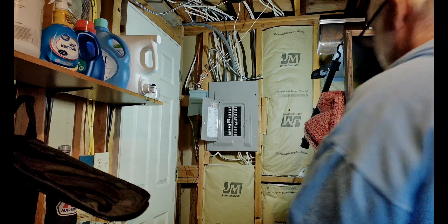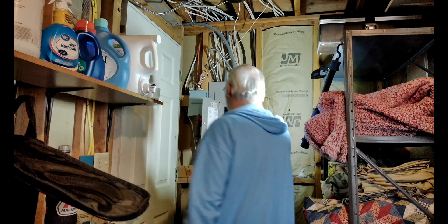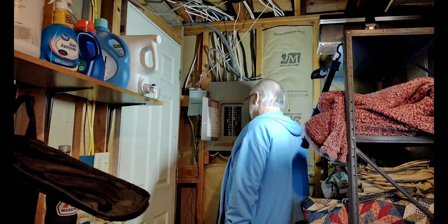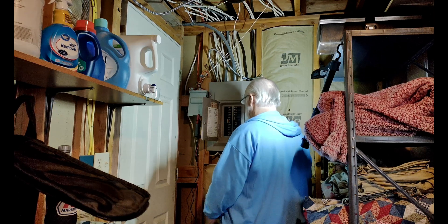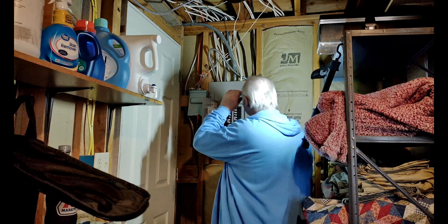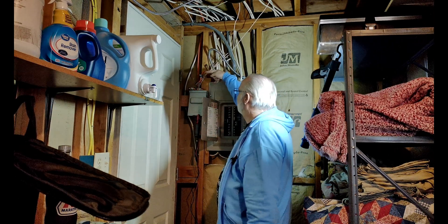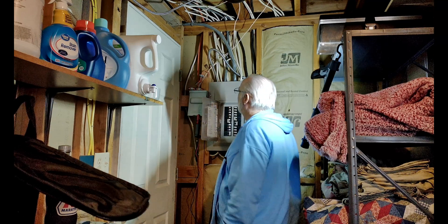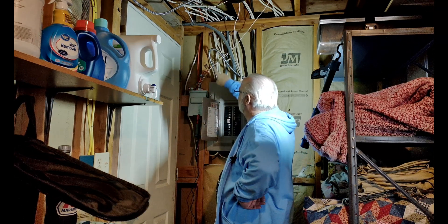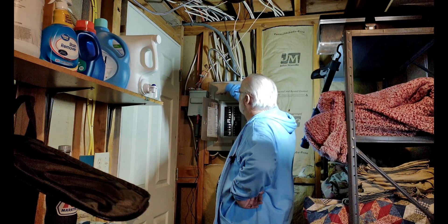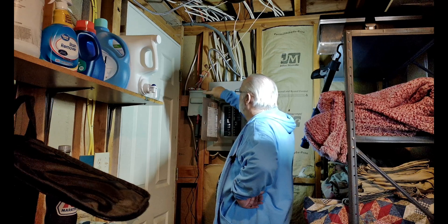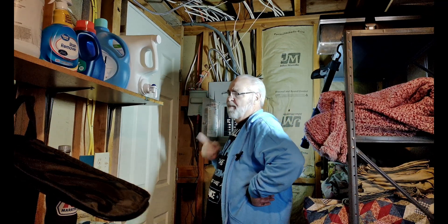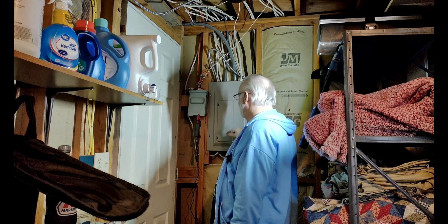We're going to have to get a different circuit breaker for this style of cabinet. We are running the 50 amp out there right now, so we're okay for the time being. But definitely this line will have to be run through here and then into this box. I'm debating upon tagging these wires into each other, putting a box in and connecting them together, and putting the disconnect out by the AC unit like it should be. So we'll decide on that.